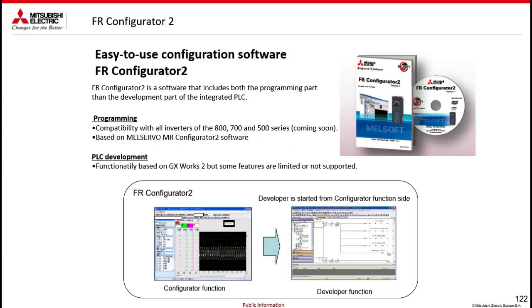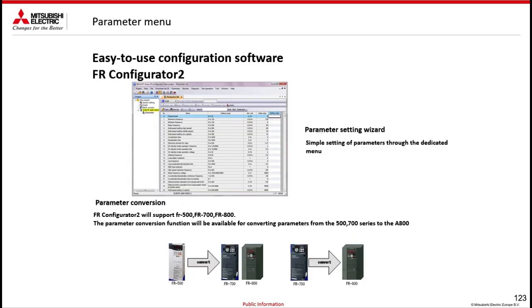Let's talk about the software now. FR Configurator 2 is the software for configuring our inverters, generally for all inverters from the A700 series to the current ones. With the software, you can do a lot of things. You can convert parameters, so maybe you have to do a revamping. You connect to the old inverter, read the parameters, and do the auto conversion to the new model, and it takes the lead in terms of autonomy.